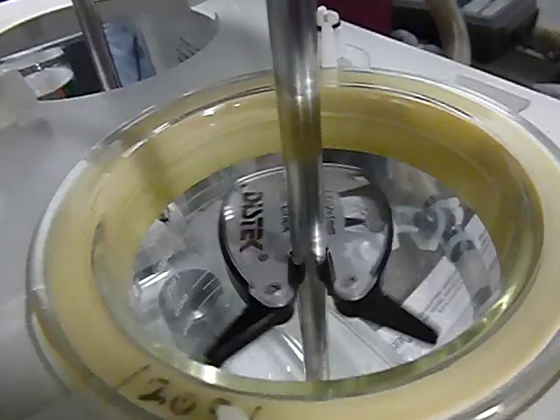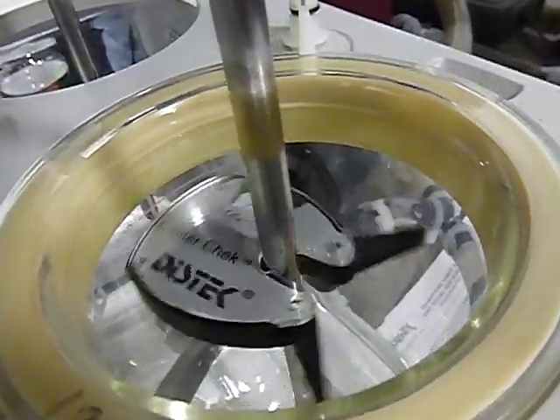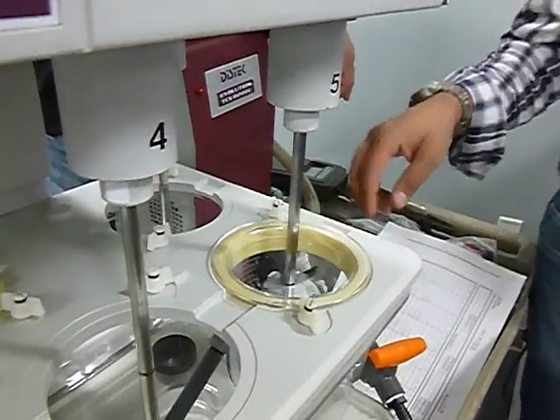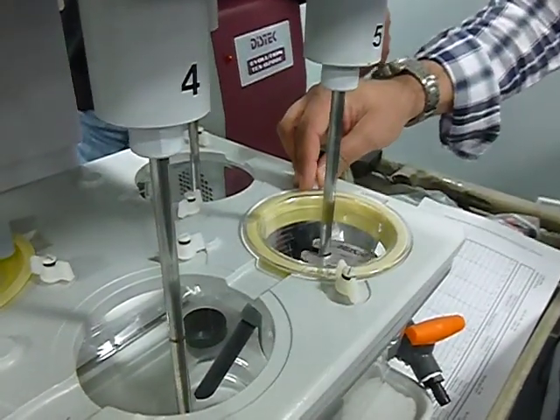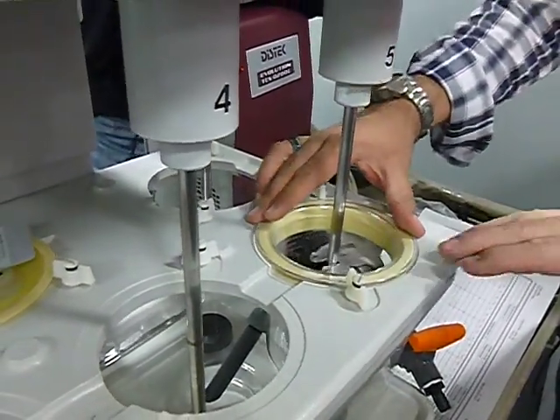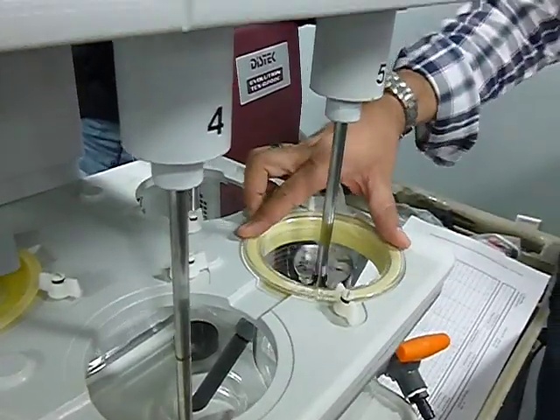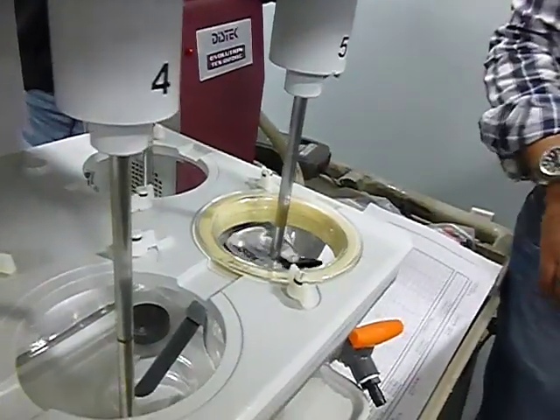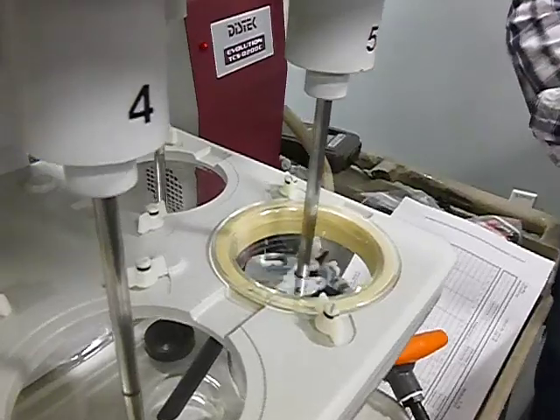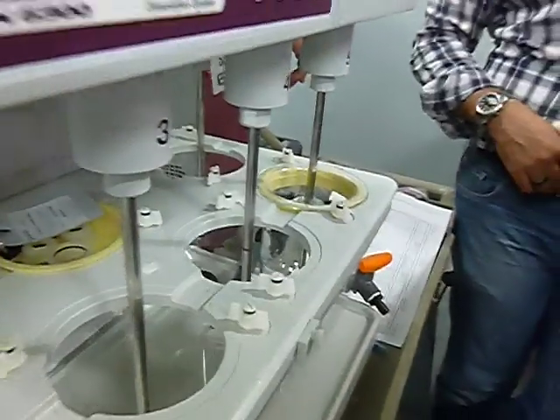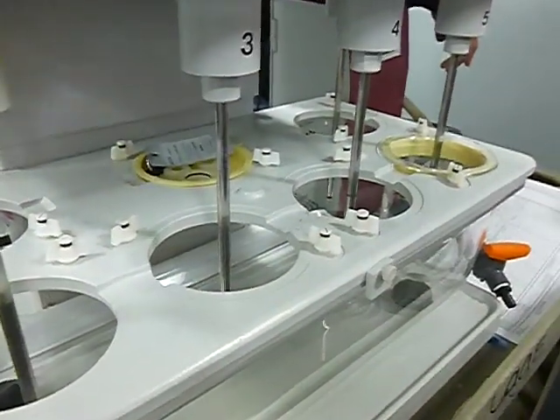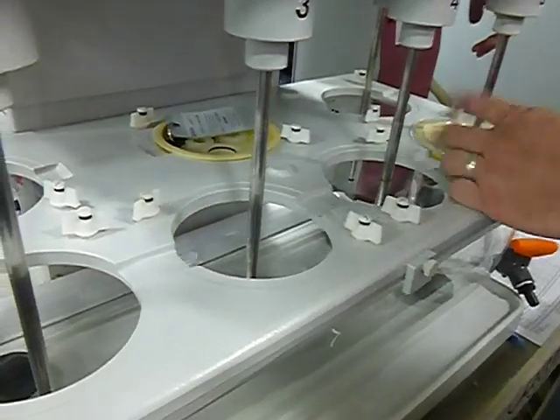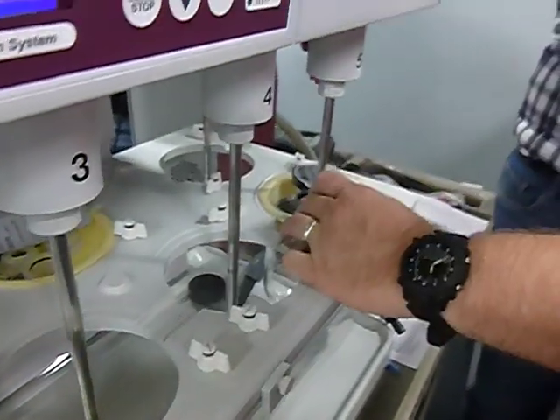Most of the scientists need to understand that when this thing's filled with water, there's buoyancy. And the only reason these clips are here is to stop the buoyancy from pushing the vessel up and out of there. Once you actually fill it with 500 milliliters or 900 milliliters or even 1 liter worth of media and do any kind of chemical testing, it's going to settle down even more. So that's all that ring is there for. That's to center it, and these clips are just to hold it down so that it doesn't go flying off anywhere. So again, it doesn't need to be over-tightened. Like I said, we adjusted these, so these are all fine.